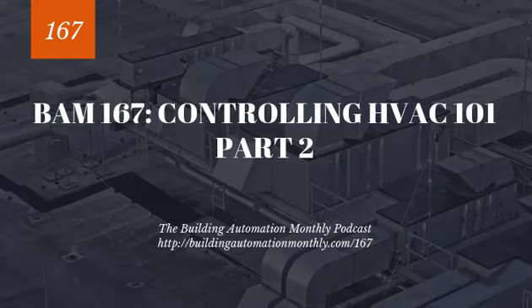So there's four main variables whenever we're working with airside systems that we need to be aware of. This is true for rooftop units, mixed air units, and 100% outdoor air units. And here are the four variables that I look at. There's a very specific reason why these are in the order they're in, but if you understand these, then what you're going to find is that your programming is going to become easier, your sequence checkouts are going to become easier, your functional test is going to become easier, because these variables build upon one another. And so it begins with our safeties, right?